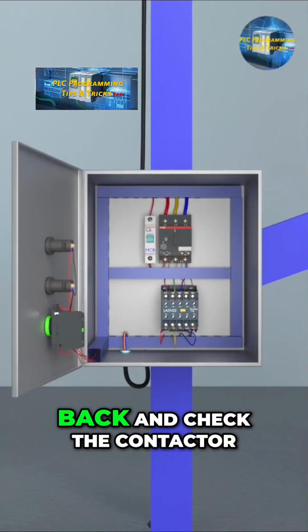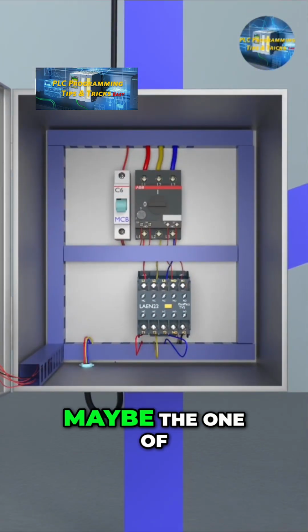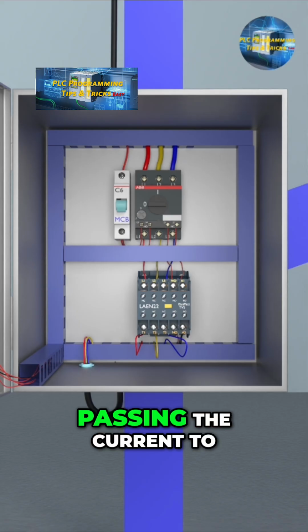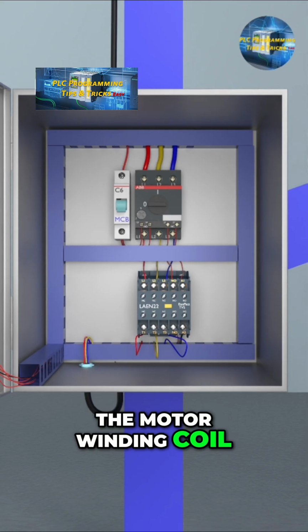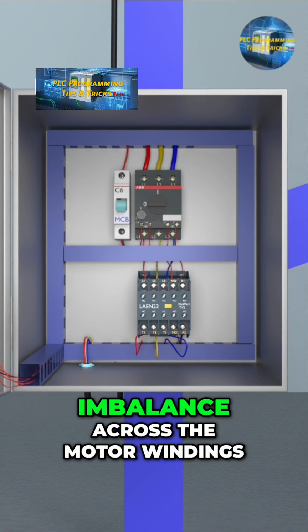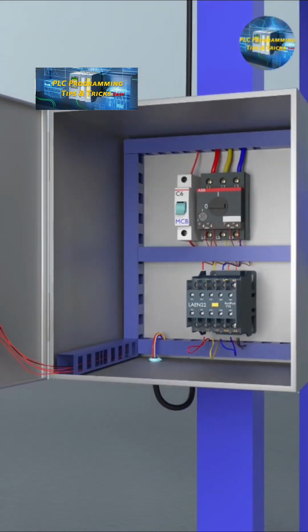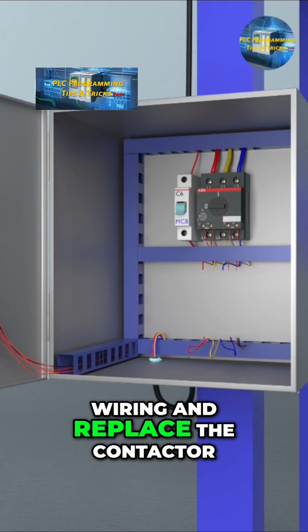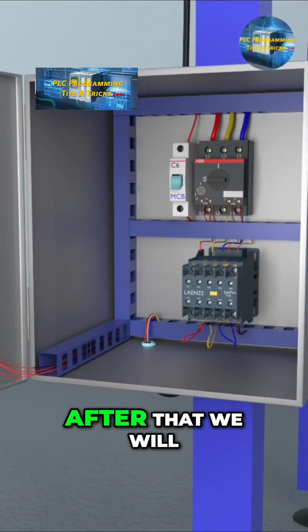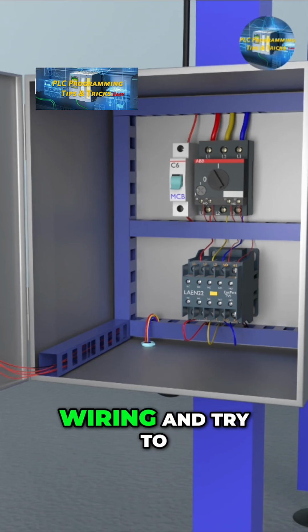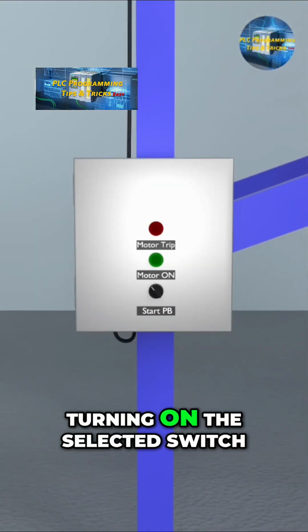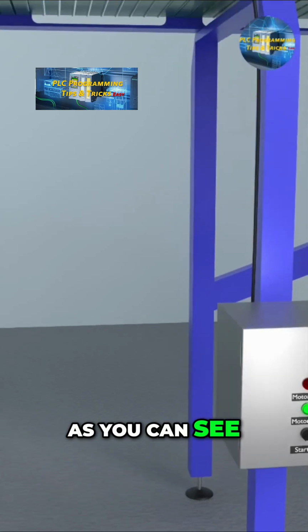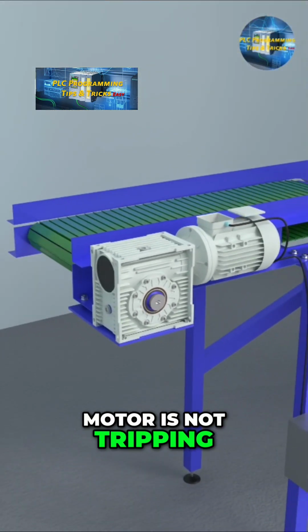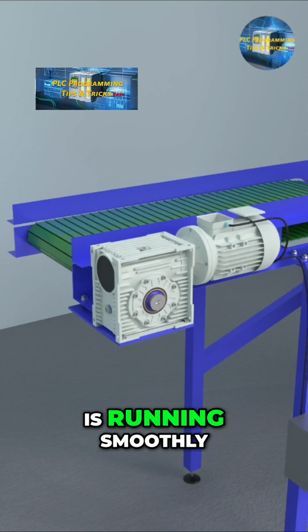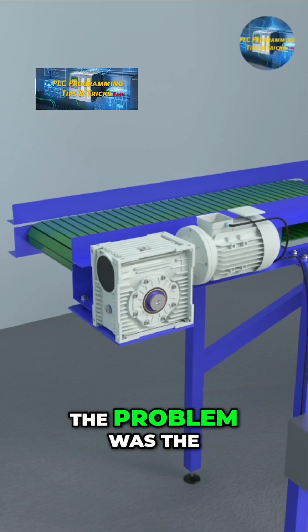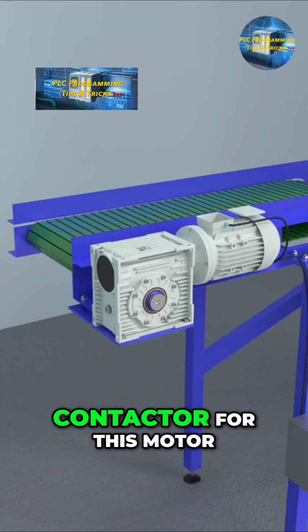Next we will go back and check the contactor. Maybe one of its contacts is not passing the current to the motor winding coil and causing the current imbalance across the motor windings. We will remove all wiring and replace the contactor. After that, we will put back all the wiring and try to run the motor by turning on the selector switch. As you can see, this time the motor is not tripping or overloading and it is running smoothly. The problem was the faulty contact of the contactor for this motor.